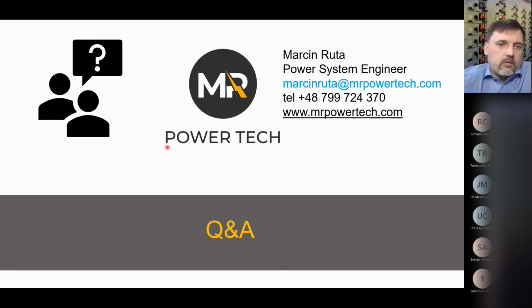I would say differential protection as a solution would be somewhere in 4th, 5th, 6th place, where I know that we, for example, have to protect the transformer better, maybe a generator, and it gives you less time. If you have 100 milliseconds or 50 milliseconds differential protection, compared to 400 milliseconds for typical overcurrent, then we take it into account for the study. So if you have differential protection, it's very nice. If you plan to have it, it's still better.